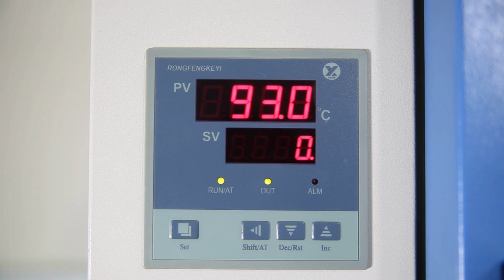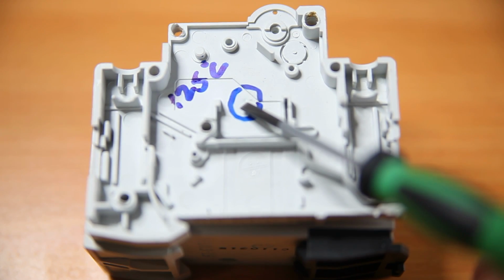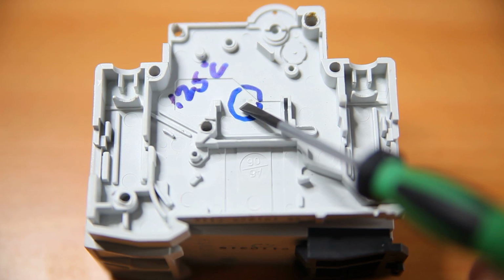The ball pressure, which is of standard weight and dimensions, is placed on top of the test specimen. The duration for withstanding the heating is 1 hour. The indentation made by the ball pressure should be below a 2 mm diameter.